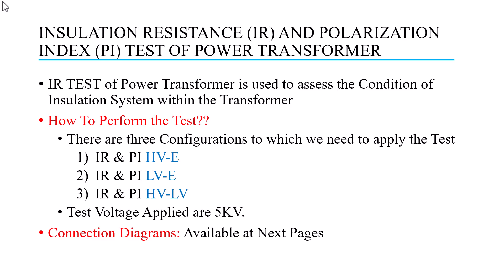The steps of how to perform the IR test involve three configurations. The first is high voltage to earth. As you know, transformers mostly have two windings, but some also have three windings. For our test case, I am considering a transformer with two windings: one high voltage and one low voltage. The three configurations are: HV to earth, LV to earth, and HV to LV.